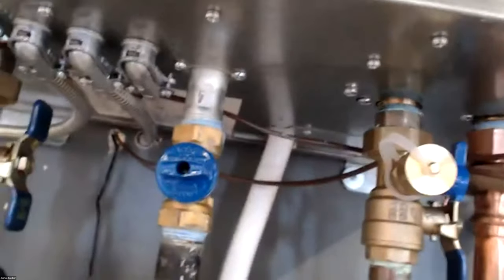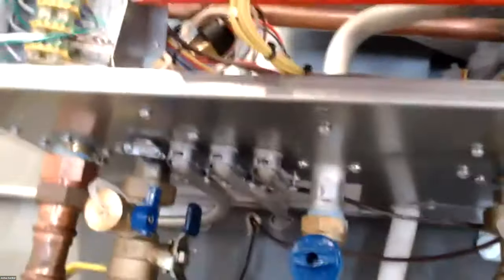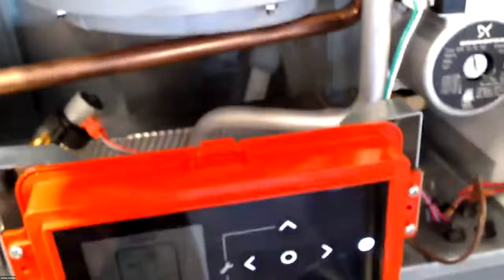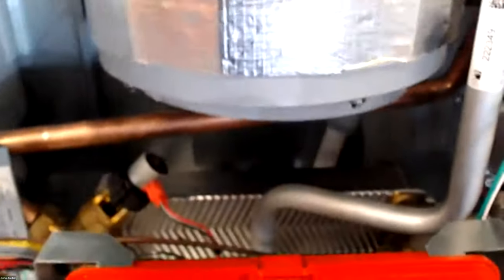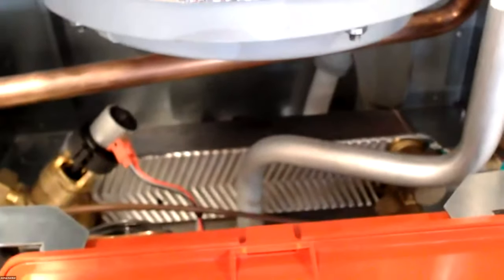We do have a lot of contractors, if the thing does plug up, that will just swap out the heat exchanger, put a new one in. With labor rates and time, it's actually cheaper in a lot of cases. So all you're going to do to swap that out is you have a screw right here, and you have a screw on the other side. You'll just loosen those up, and this flat plate heat exchanger just pulls straight out. There's no reason you need to pull out the control, the solenoid, or any of that piping to get that flat plate heat exchanger out. You can do it with just removing those two screws.